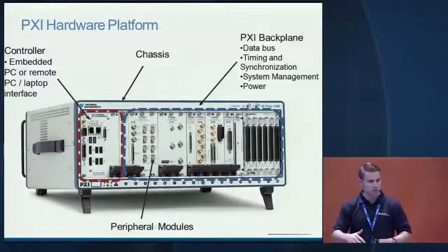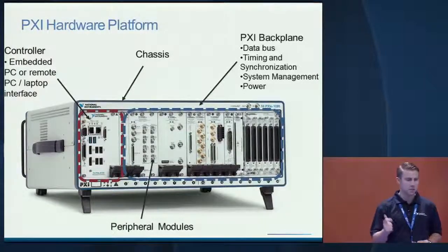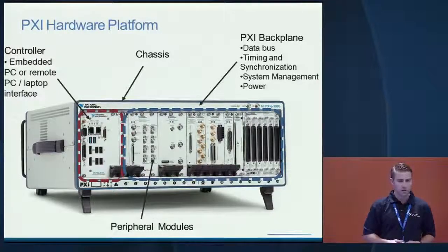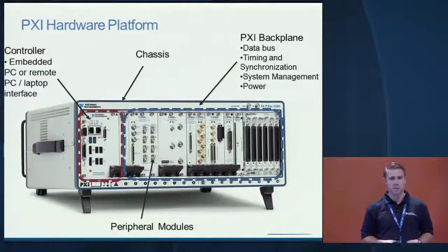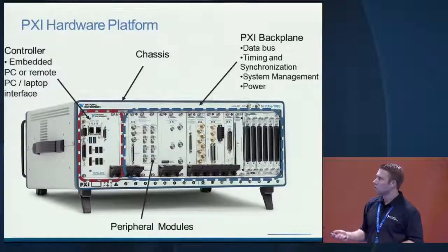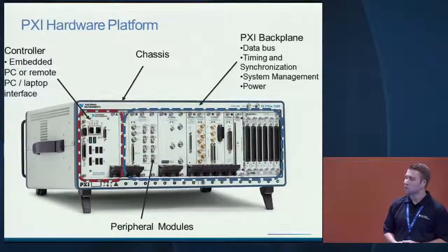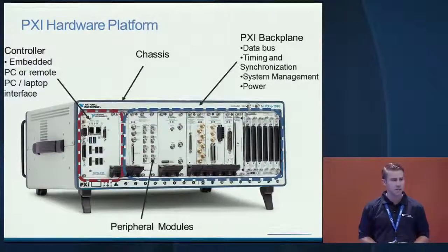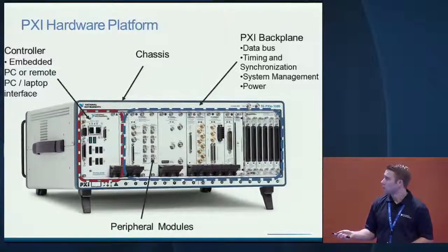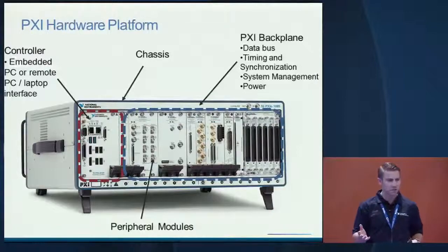The PXI platform is comprised of three or four main components. First is the chassis — this is our shell, providing all the physical connections. On that chassis is the PXI backplane, which includes the data bus, timing and synchronization, system management bus, and power and cooling, which are very important for these compact instruments that tend to generate a lot of heat. Next is the controller, which can be an embedded PC, a remote PC connected via an MXI connection, or a laptop interface using an ExpressCard. Finally, there are peripheral modules — an essentially infinite combination of modules for your specific test application.